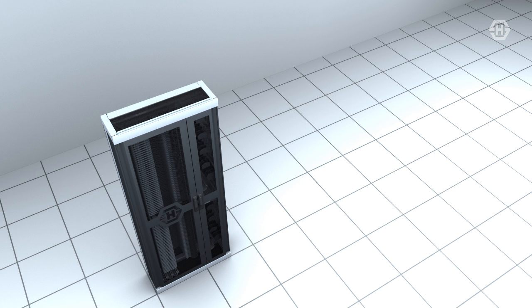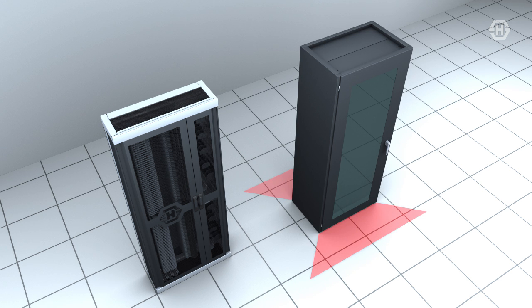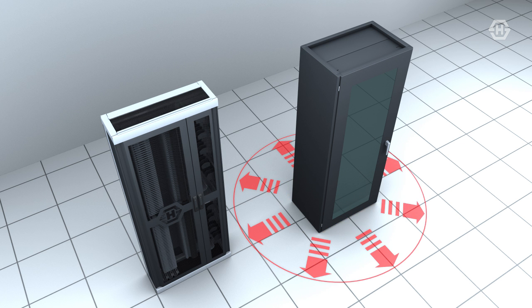The limitation of having to access connectivity from the rear side of the cabinet can often contribute still further to the overall space consumption of a single cabinet. Maintenance space around the cabinet has to be kept free for walkways and door clearance, and therefore a 600 millimeter cabinet can actually require a functional depth of as much as 1800 millimeters just to open the doors.